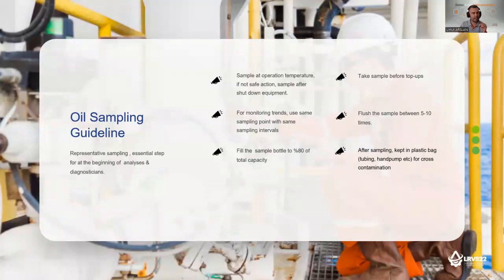Take a look at the oil sampling guideline. Sampling at operating temperature is really important. When you sample without operating temperature, such as cold, you see different behavior of the oil, because we are looking at the characteristics of the oil at operating temperature. For example, sampling from engines when cold, you can find higher water content too, or sampling hot, maybe you can get higher results due to water condensation. I experienced this situation, especially for transformer oil sampling.